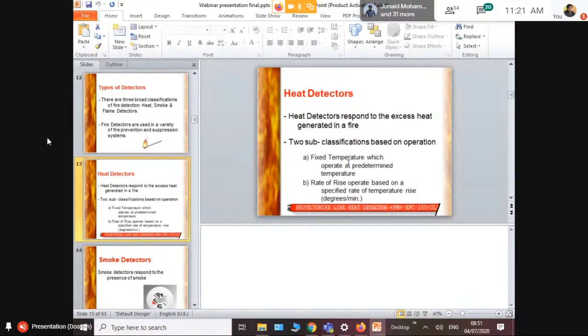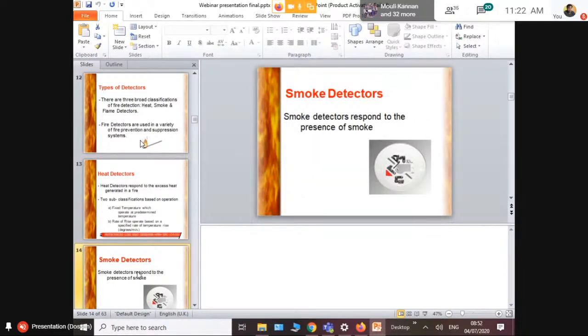And what is the rate of rise? Rate of rise is like it has a standard wherein, say for example, 2 degrees per minute is the set value in the detector. So when the temperature increases by 3 degrees per minute, then there will be a notification sent to the control alarm and an alarm signal will be initiated.